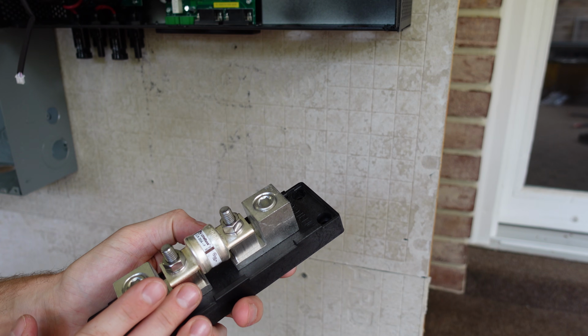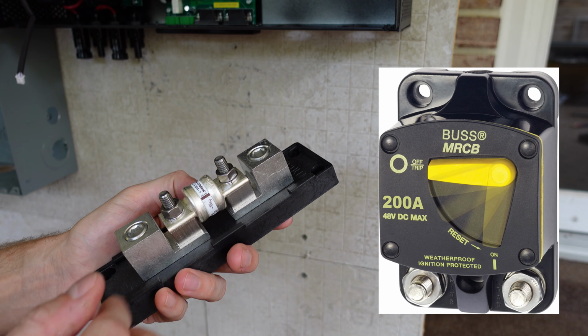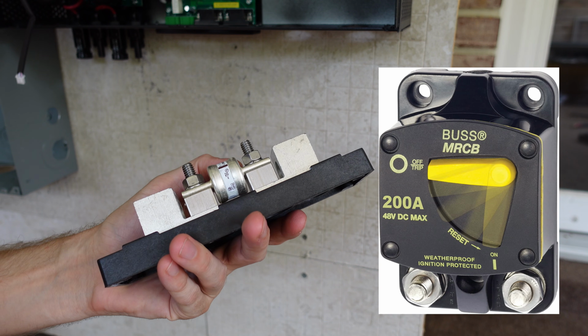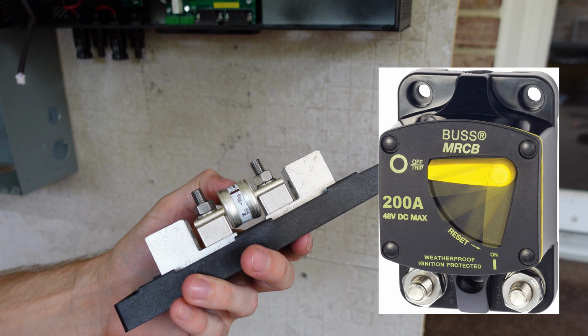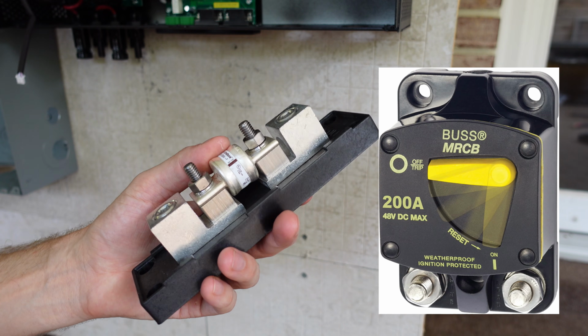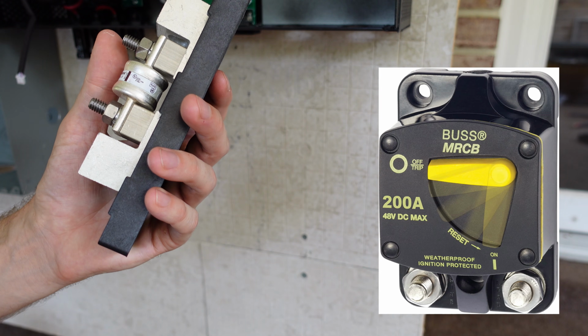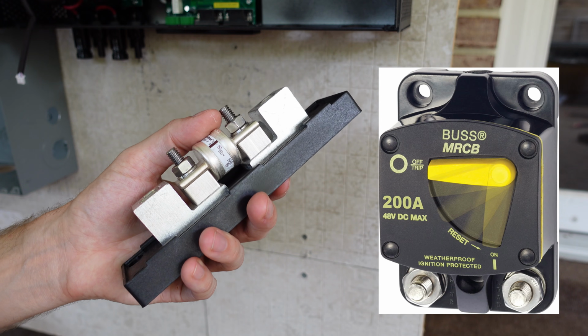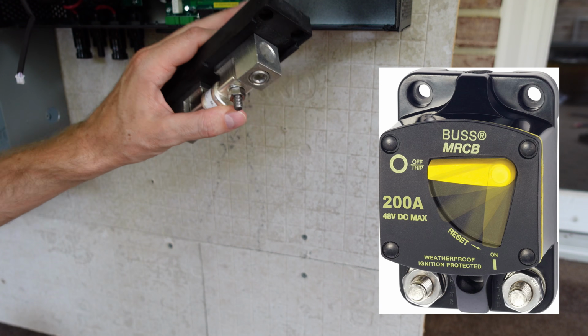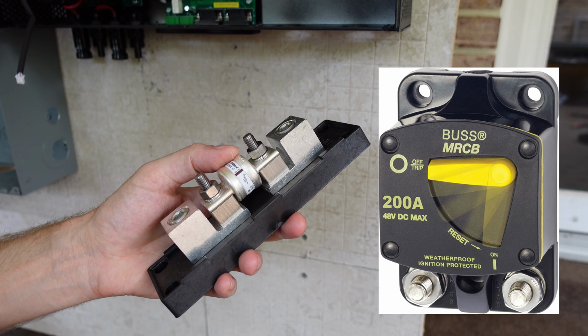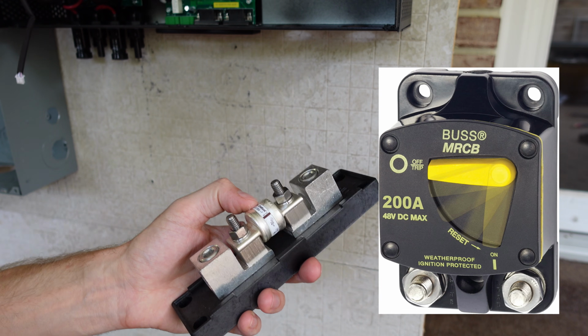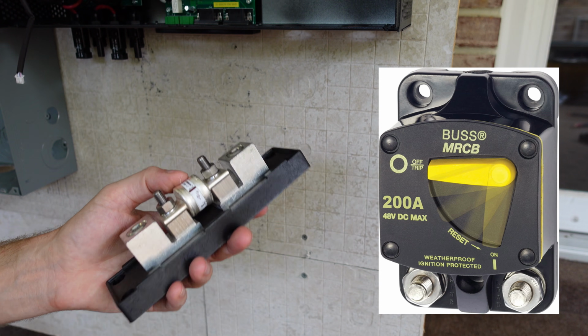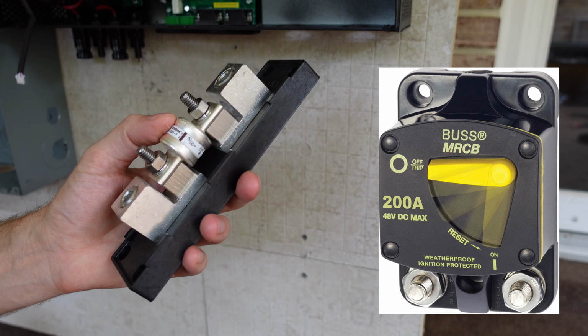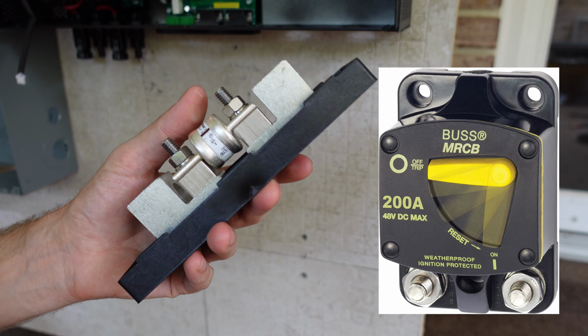I've seen some people use those Blue Sea Systems, the cheap flippy type breakers, and those say they're rated for 48 volts, but to my knowledge, per a question I asked directly to Blue Sea Systems, those cannot support up to 60 volts, which is required by these inverters. So my understanding is that those are hard limited to 48 volts. Some people are using them, some people seem to be fine using them, but when the company told me they don't go up to 60 volts, I didn't want to use them.